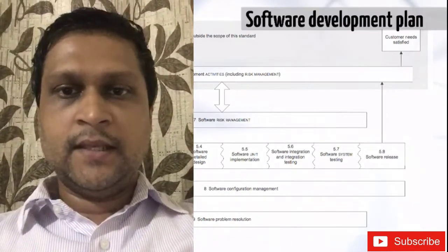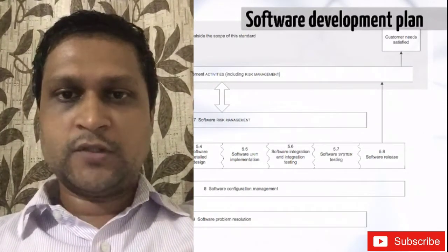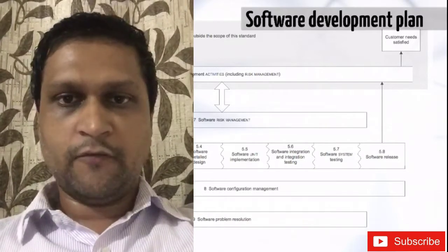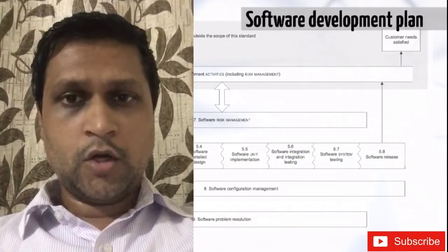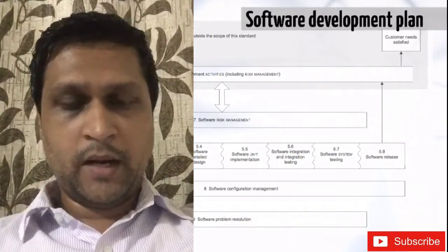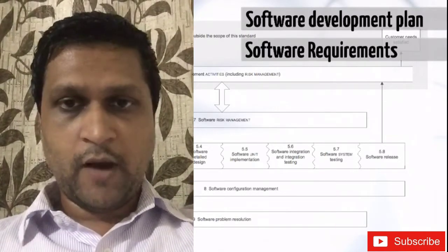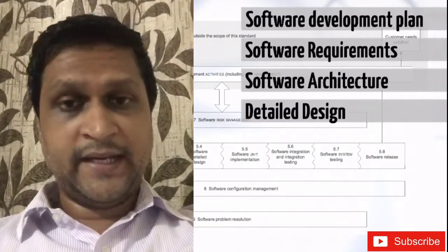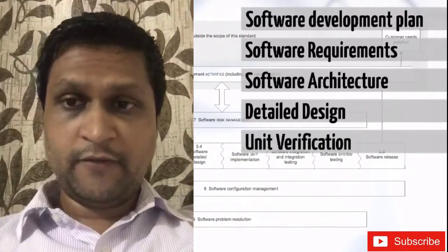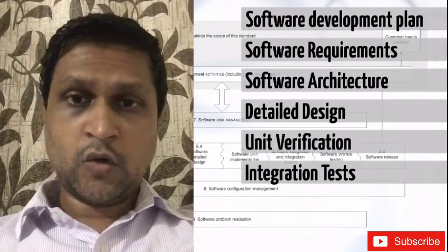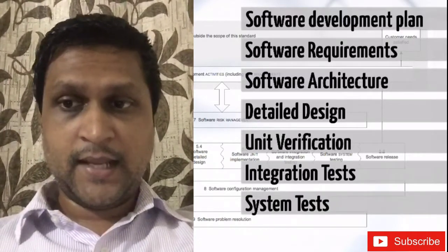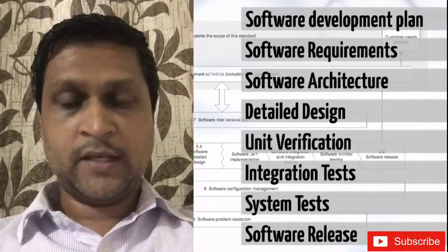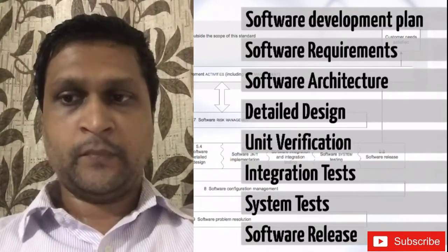Now the IEC 62304 standard talks about the software development plan. There should be a clear plan for the software development. It also talks about the clear requirements of the software in the software requirements. It also describes the software architecture, the detailed design, and the unit verification. It also talks about the integration testing, the system test, and the software release. If you comply with these nine or more documents, then you meet the IEC standard.